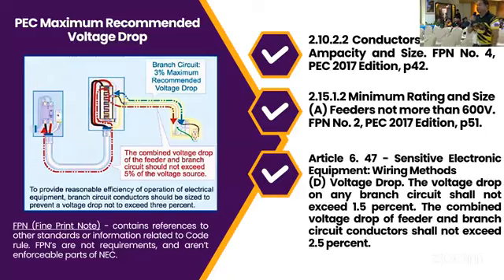So PEC maximum recommended voltage drop. As you can see, branch circuit, 3% maximum recommended voltage drop. Then the combined voltage drop of the feeder and the branch circuit should not exceed 5% of the voltage source. Or else pag lumampas dyan, you need to resize, upgrade from, halimbawa, 50 mm square to 60 mm square, as long as hindi lumampas sa 5%.